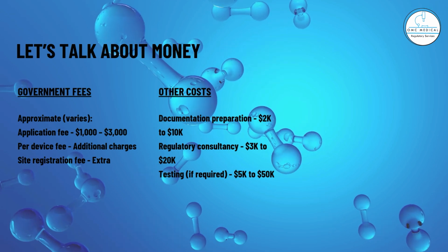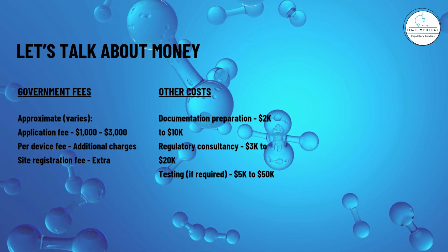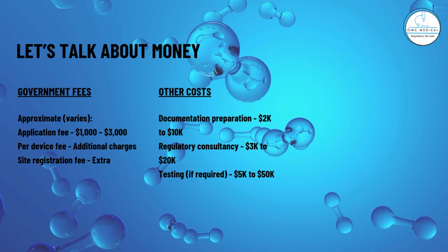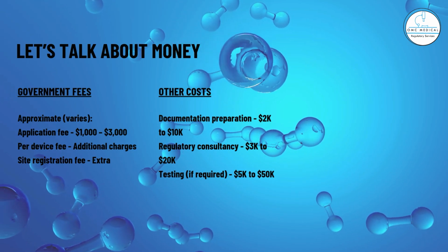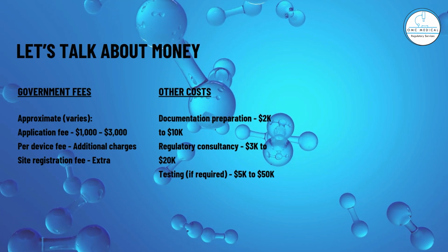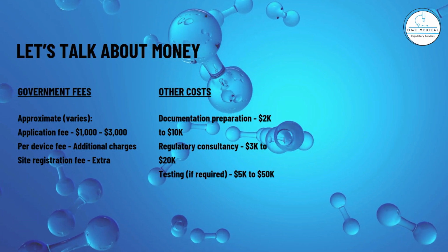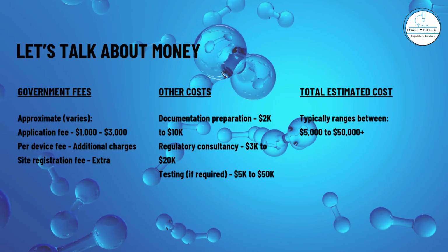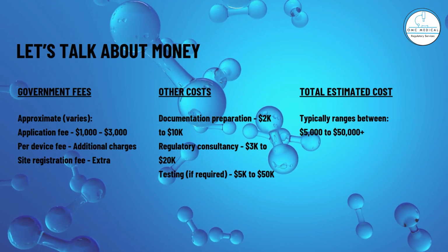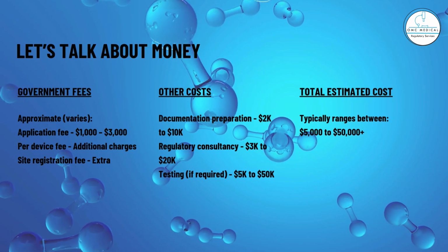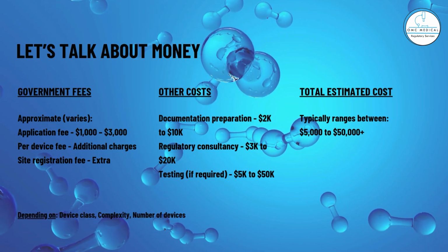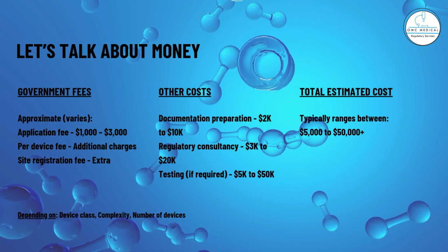Other costs. Documentation preparation, $2,000 to $10,000. Regulatory consultancy, $3,000 to $20,000. Testing, if required, $5,000 to $50,000. Total estimated cost typically ranges between $5,000 to $50,000 plus, depending on device class, complexity, and number of devices.